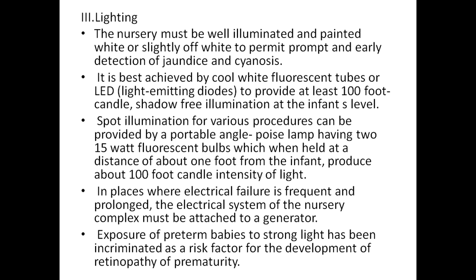In places where electrical failure is frequent and prolonged, the electrical system of the nursery complex must be attached to a generator. Exposure of preterm babies to strong light has been incriminated as a risk factor for development of retinopathy of prematurity. Temperature. The temperature of the nursery complex must be maintained between 26 to 28 degrees Celsius in order to minimize the effect of thermal stress on the babies. It is best achieved by centralized air conditioning having temperature control knobs in the nursery. The air movement should be so designed that draught is minimized.